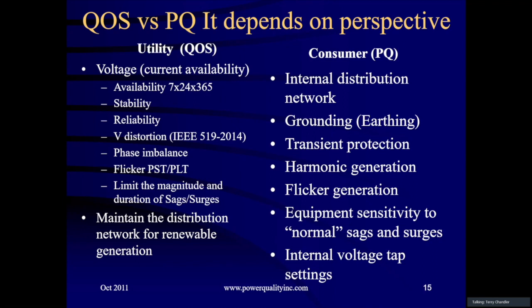The other issue is internal voltage tap settings. So almost all of the large facilities have their own step-down transformers, and they're responsible for the voltage tap settings. One of my more interesting case studies is a data center that was built specifically in a building, a 200,000 square foot building for offices and data center. And when they built it, they made an error in the expected electrical voltage. And they ended up having to change all the taps on the transformers to the highest level, and it still wasn't high enough. So that was a pretty expensive change when it came down to changing the incoming voltage.